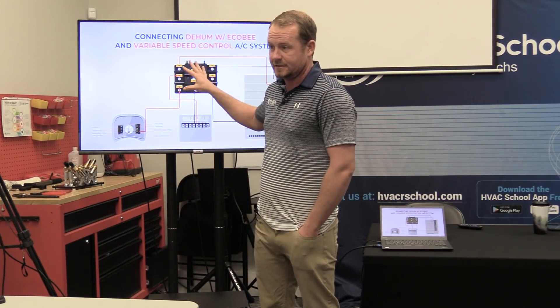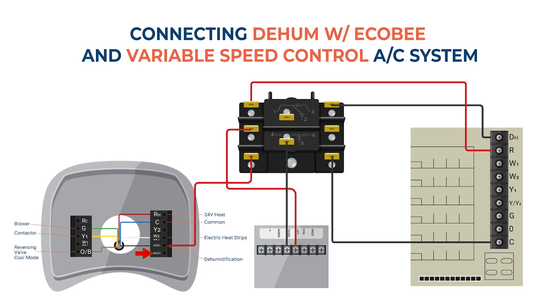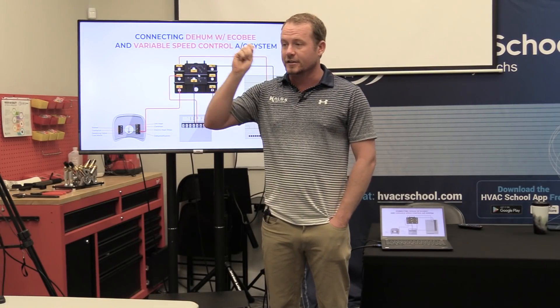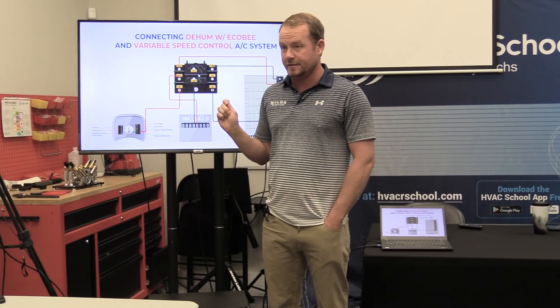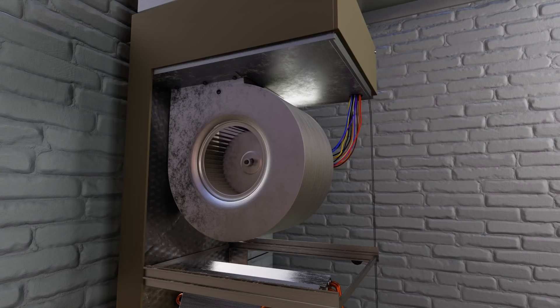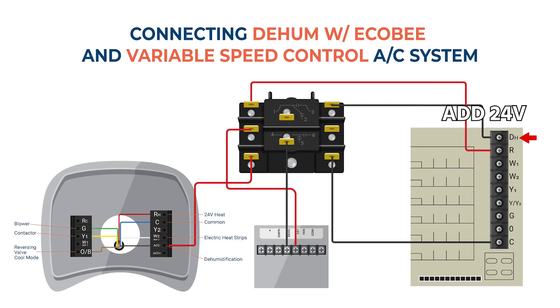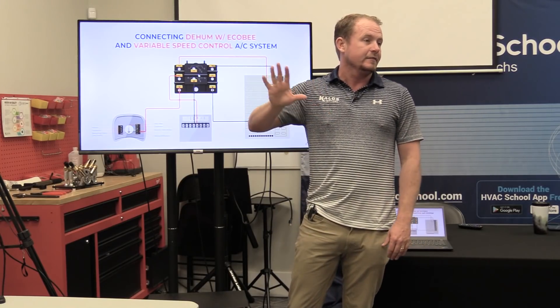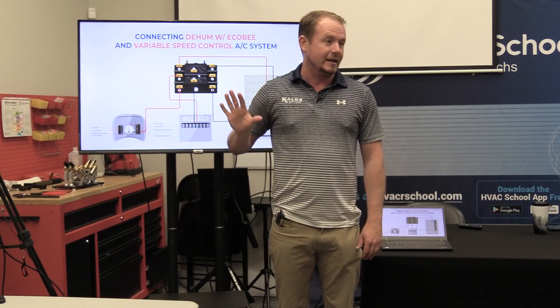If you were going to set this up without this mess, that's how you would set it up. ACC plus to DH. And you would set it up with unenergized to dehumidify, energized to not dehumidify, to run full speed. Because that's all we're saying. We're saying blower run full speed, blower not run full speed. Blower run full speed equals add 24 volts to DH. Blower run less than full speed, you drop DH, and then it ramps down.